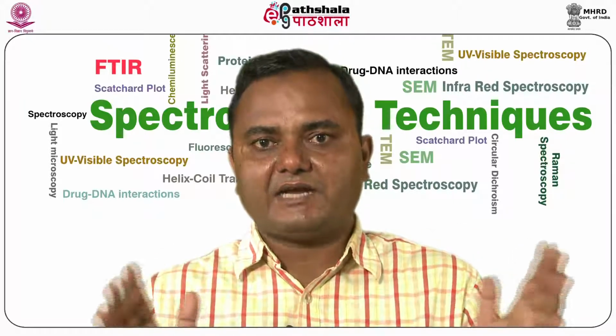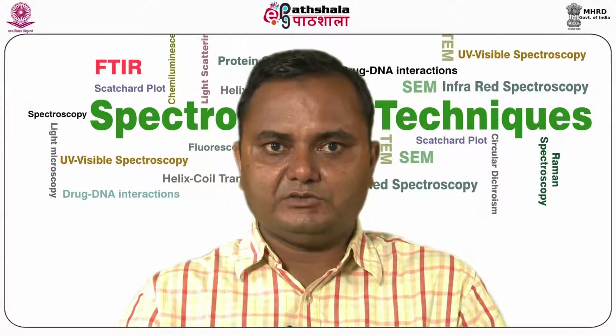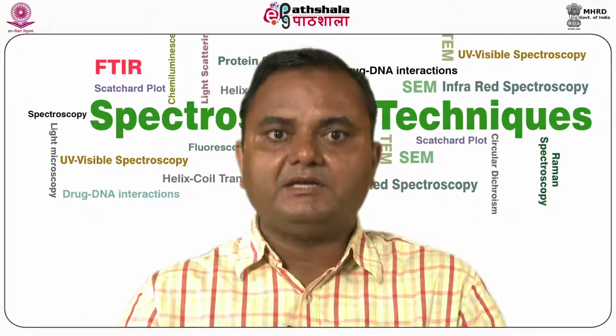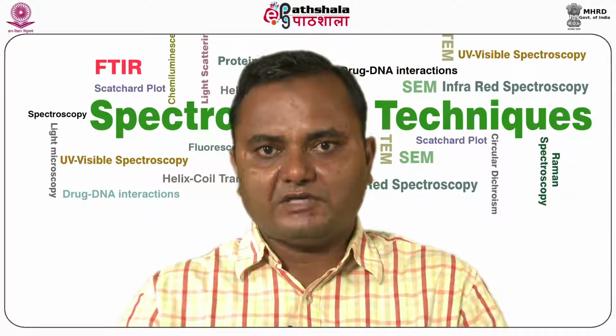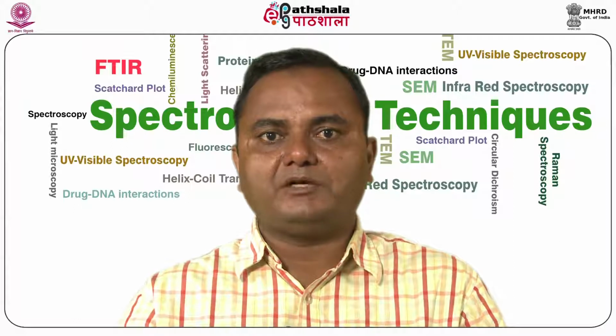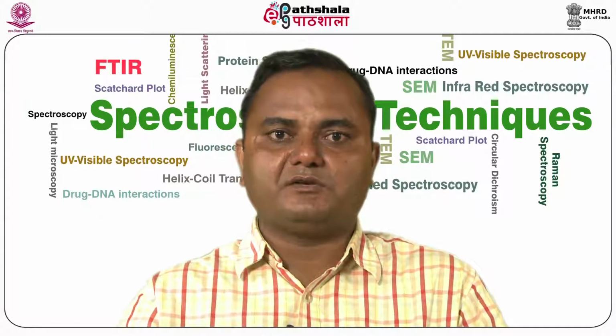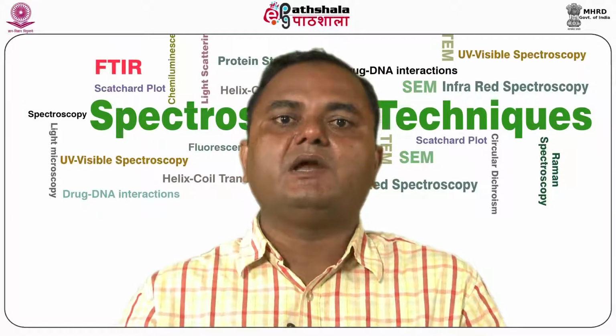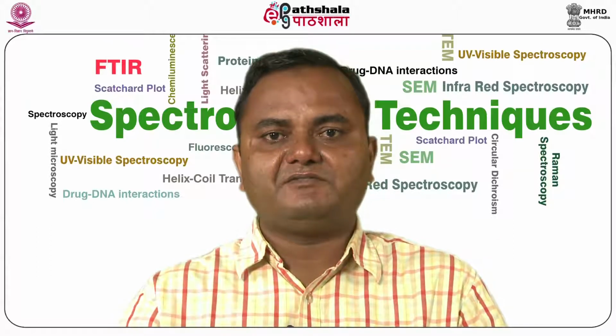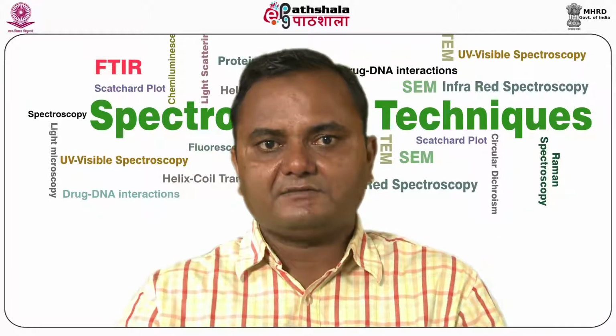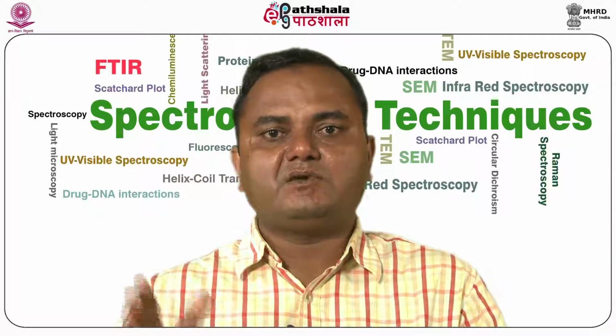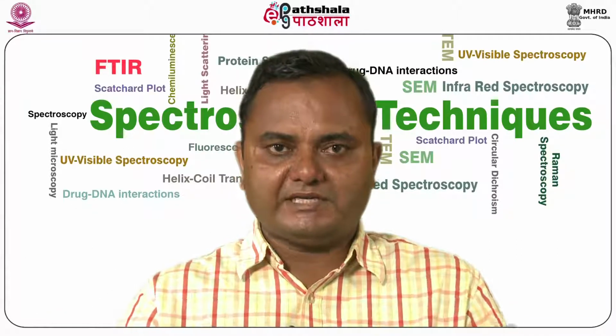Also important are the location of the green fluorescent protein versus its confinement to small subregions of the cell or tissue, quality of excitation and emission filters and dichroic mirror, and sensitivity, noise, and dark current of the photodetector.